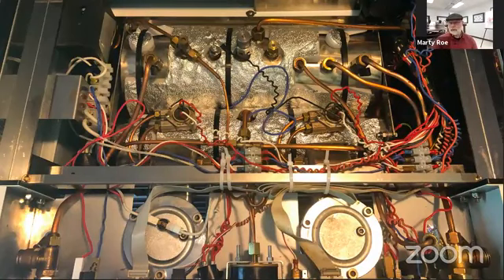And what you had was a chain of events: the leak started first, and those coils aren't designed to be wet. There's tiny wire wrapped hundreds of times around a spool inside that black box, and they're tiny, so what you end up with is a small electrical short inside there, and it just burns it up. You saw that.